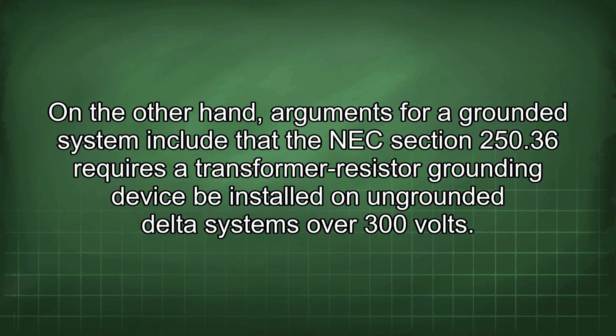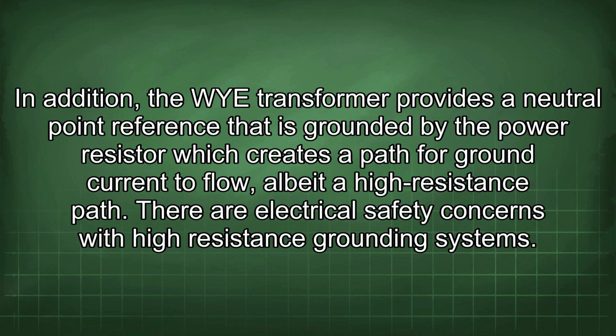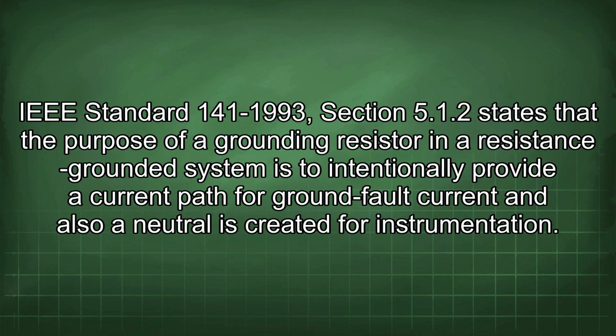On the other hand, arguments for a grounded system include that the NEC section 250.36 requires a transformer resistor grounding device be installed on ungrounded delta systems over 300 volts. In addition, the WYE transformer provides a neutral point reference that is grounded by the power resistor, which creates a path for ground current to flow, albeit a high resistance path. There are electrical safety concerns with high resistance grounding systems. IEEE Standard 141-1993, Section 5.1.2 states that the purpose of a grounding resistor in a resistance grounded system is to intentionally provide a current path for ground fault current, and also a neutral is created for instrumentation.